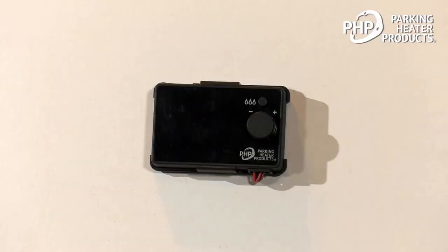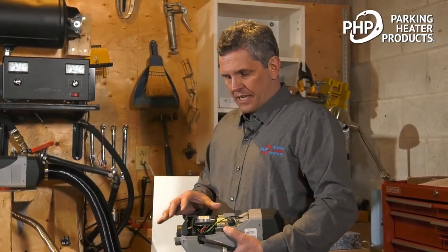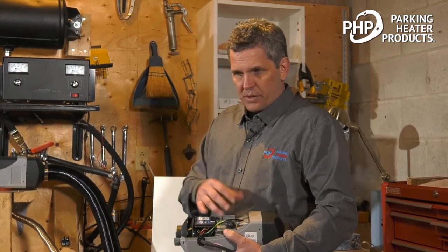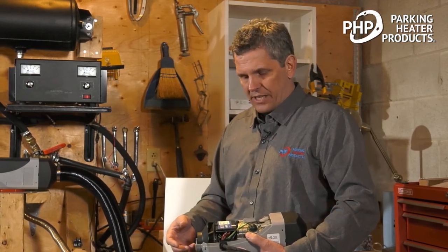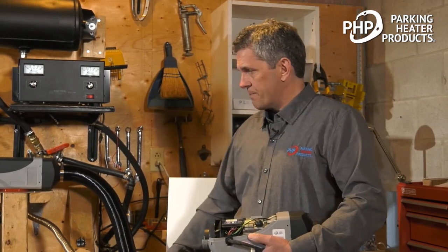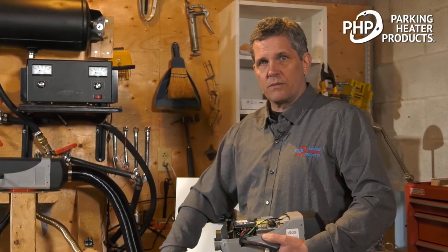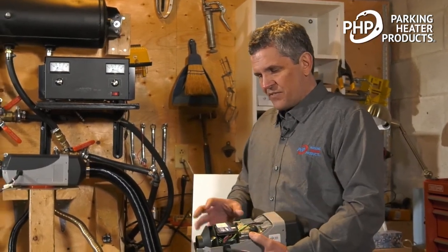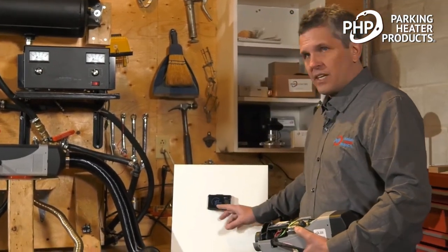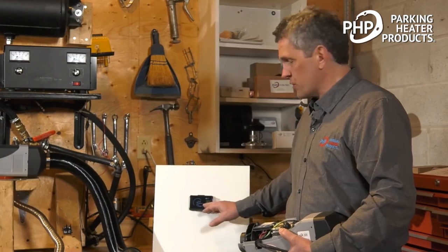The heater has a number of different safety systems. It is monitoring the temperature, so if there's a blockage and an overheat occurs, the system will shut down. If there is a flame out, the heater will try to restart. If the flame does not establish on startup, the heater will shut down. If there's a break in any of the circuits, the heater will shut down. If it has been operating, then it'll conduct a 3-minute cool down before switching off completely. If there is a fault, then we'll see a fault code displayed on the control switch.